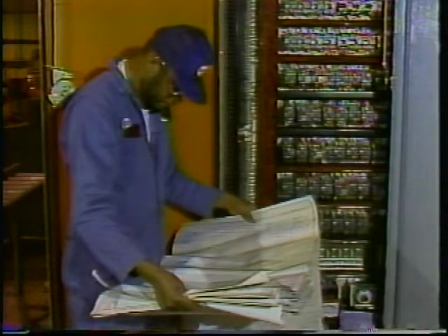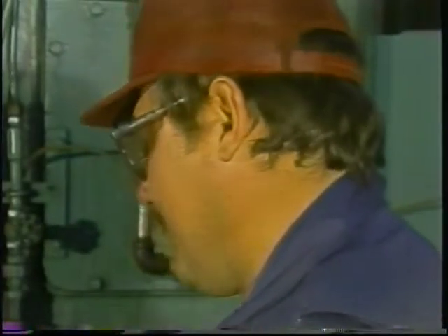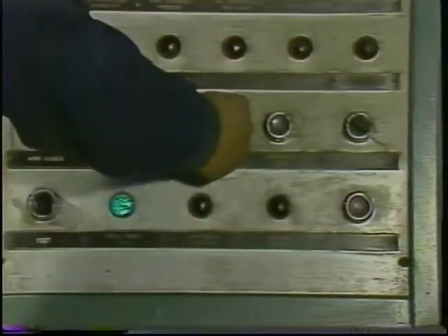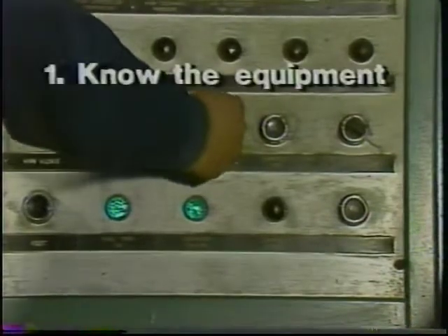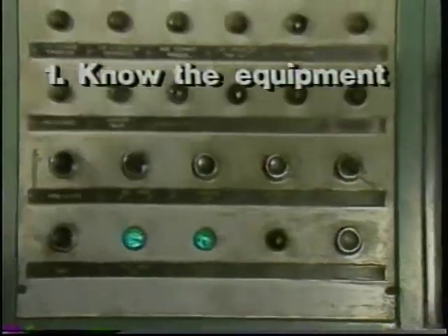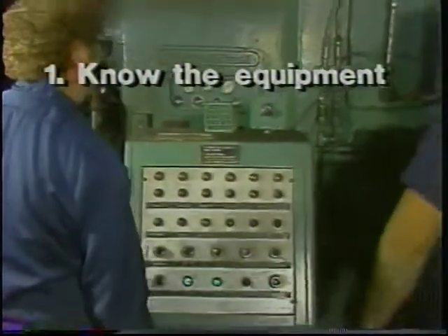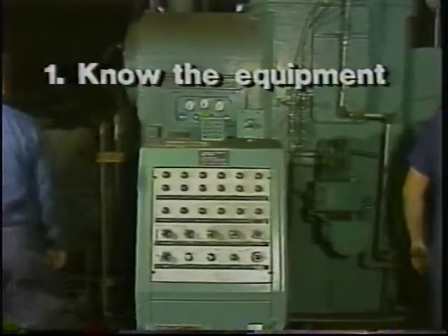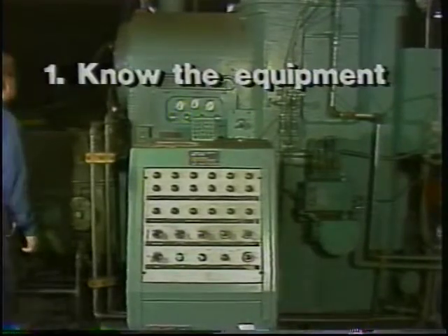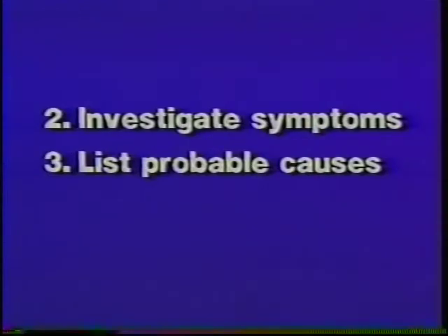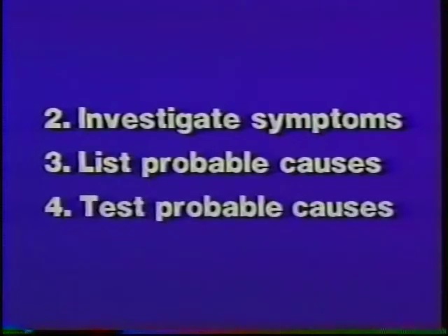Troubleshooting is a science. To troubleshoot effectively, first of all, you've got to know how the motor is supposed to work, how much current it should be drawing, for example, or how to start it. And it helps if you know the history of the equipment and whether it's been breaking down frequently. Then, to track down the trouble, you must follow a logical, step-by-step procedure. You investigate the symptoms. Based on what you discover, you analyze the problem and list the probable causes. Then you perform systematic tests to eliminate possibilities until you locate the trouble.